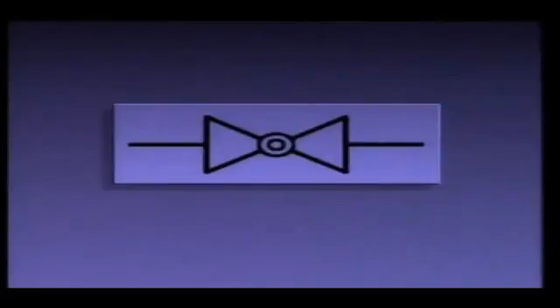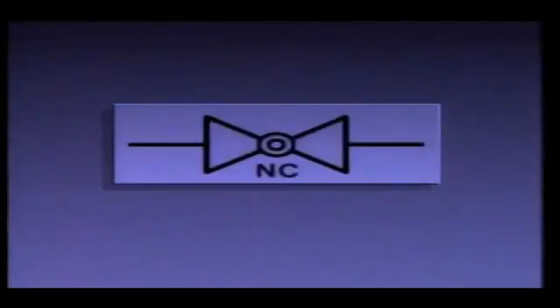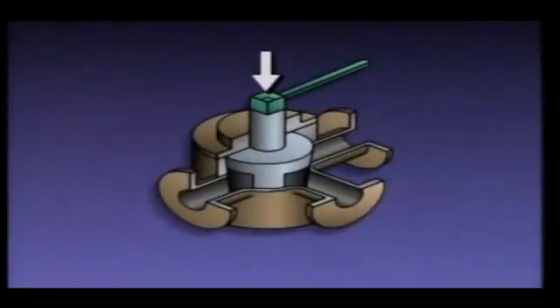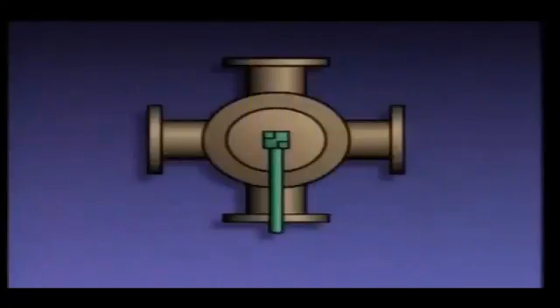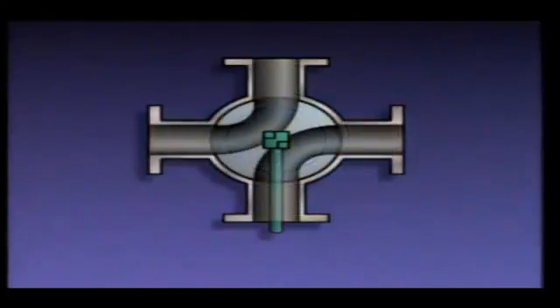On a piping system diagram, a ball valve symbol generally looks like this. If the symbol looks like this or has the letters NO beside it, the valve is normally open; if filled in or marked NC, it is normally closed. A needle valve generally looks like this on a diagram. Multi-port plug valves usually have L-shaped markings on their handles. Three-way plug valves have one L and four-way plug valves have two, allowing you to determine flow direction by comparing the L positions to the piping.